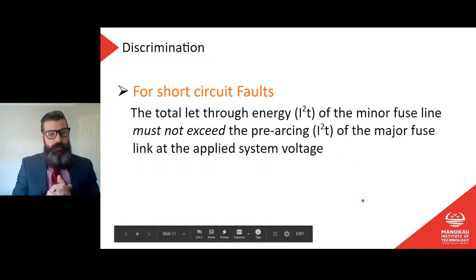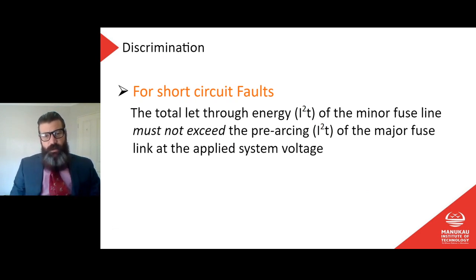Discrimination for short circuit faults. The total let through energy, so I squared T, it's current squared times time, of the minor fuse link must not exceed the pre-arcing I squared T of the major fuse link at the applied system voltage. Whew. If any of you know what that means, call me. No.